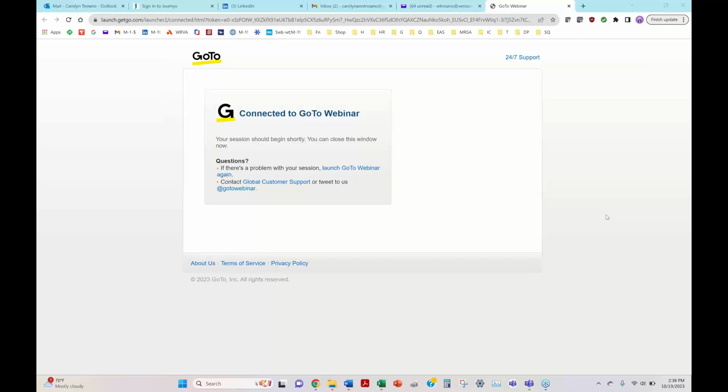Sure. It's very important that if FDA is coming in, you try to get a scope memo up front to know what they're going to be looking at. And they say, we're going to come in and look at 2 of your systems. The first thing they're going to do is ask you for your GXP system inventory. And when you show them that, there's no guarantee they're going to pick the top 2 systems. You don't know what systems they're going to pick to audit.